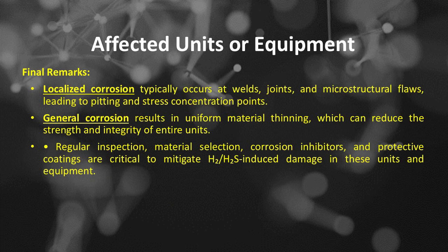The final remarks from high-temperature hydrogen or H2 and hydrogen sulfide or H2S corrosion that we can take are included. Localized corrosion typically occurs at welds, joints, and microstructural flaws, leading to pitting and stress concentration points. General corrosion results in uniform material thinning, which can reduce the strength and integrity of entire units. Regular inspection, material selection, corrosion inhibitors, and protective coatings are critical to mitigate hydrogen or H2 and hydrogen sulfide or H2S induced damage in these units and equipment.